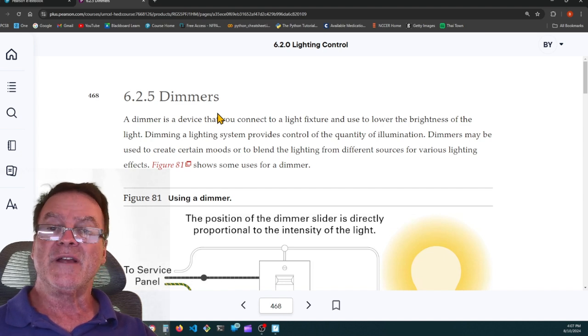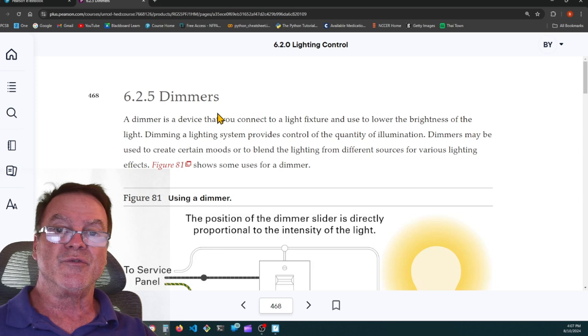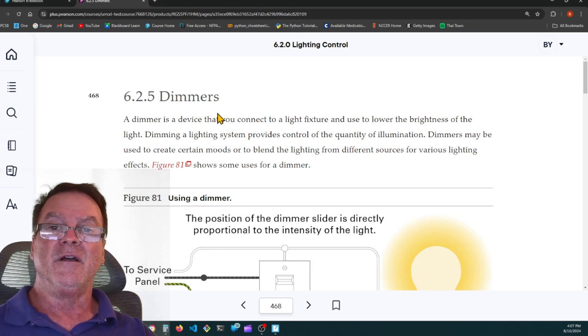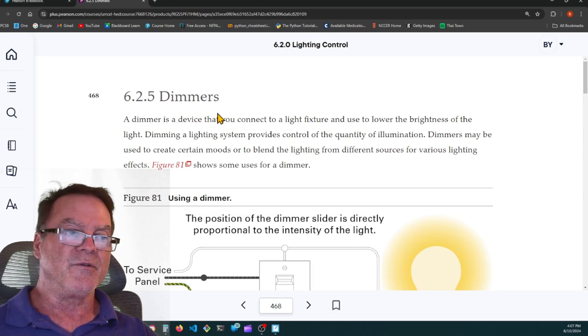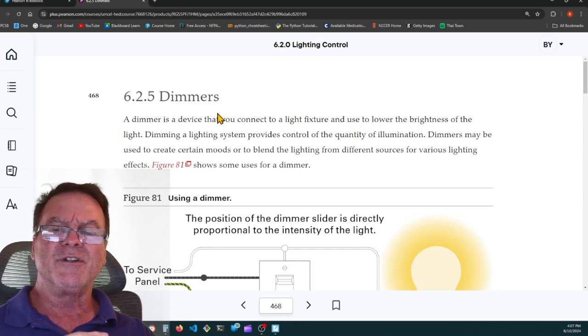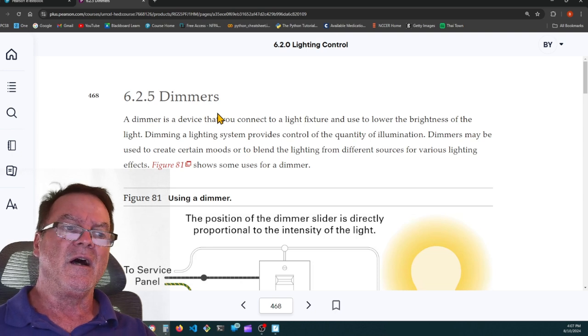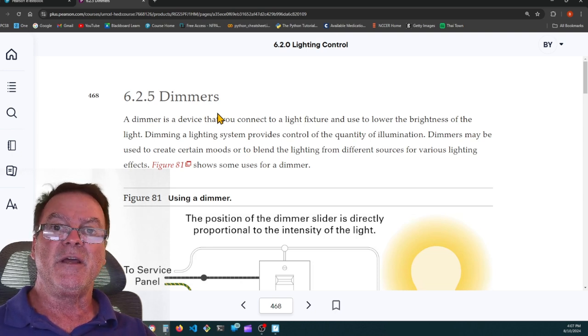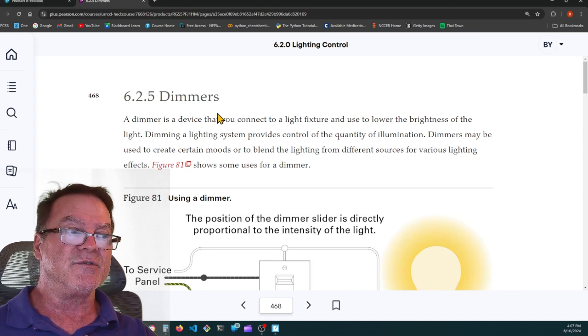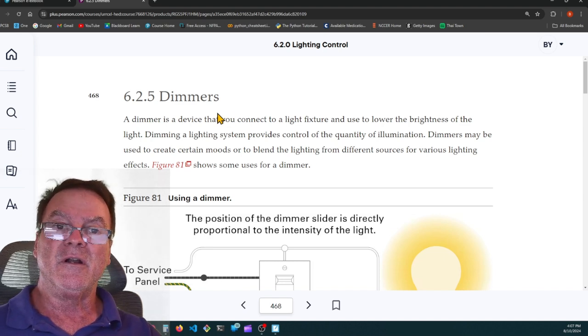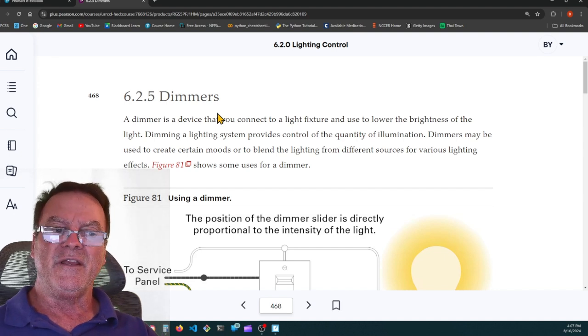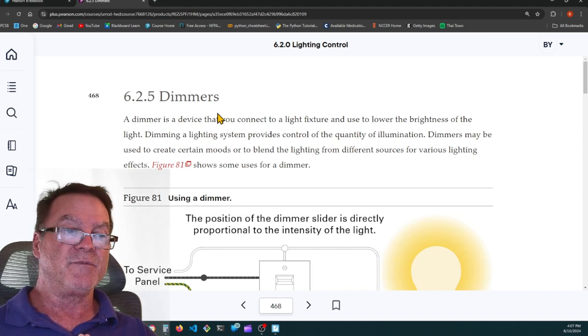Then they came out with fluorescent, compact fluorescents, and you couldn't use a rheostat on fluorescent lighting. So they came out with a dimmer that did not dim the voltage, it dims the current. We used to have to buy a special dimming ballast for fluorescent lights, and we had to use a special fluorescent dimmer to make sure that we didn't burn up the ballast in the fluorescent light. If you dimmed the voltage to the fluorescent ballast, you would burn it up. So they would use special dimmers.